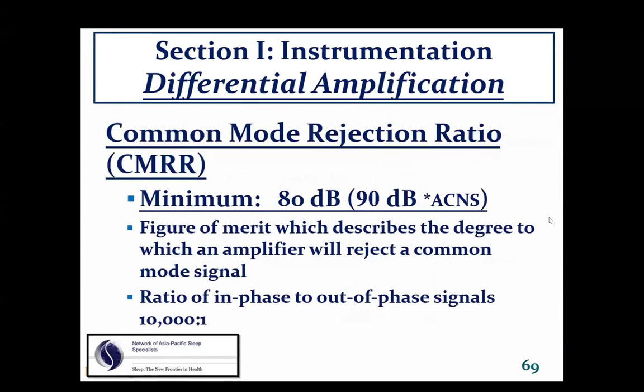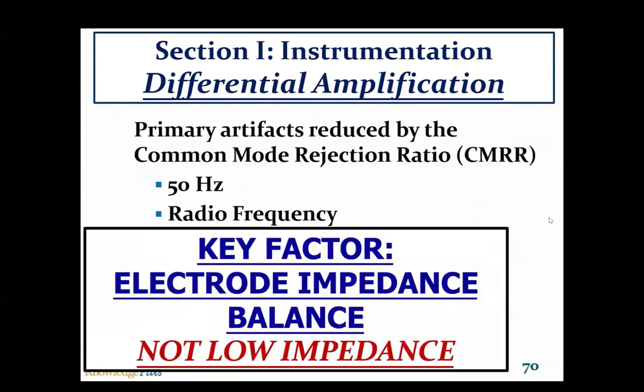In the guidelines, it says common mode rejection ratio, minimum should be 80 dB. 90 dB is what ACNS states. Now, what that rejection ratio is, it's a figure of merit which describes the degree to which the amplifier will reject a common mode signal. So it deals with the quality of the ability of the common mode rejection to influence our recording. They also say the ratio of in-phase to out-of-phase signals should be 10,000 to 1 minimum. Now, I don't think you have to worry about this because really all of our equipment now blows it out of the water, far above minimum requirements. The primary artifacts reduced by common mode rejection ratio is 50 hertz and radio frequency noise.